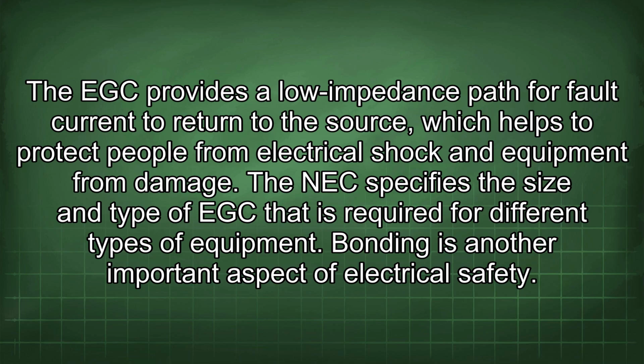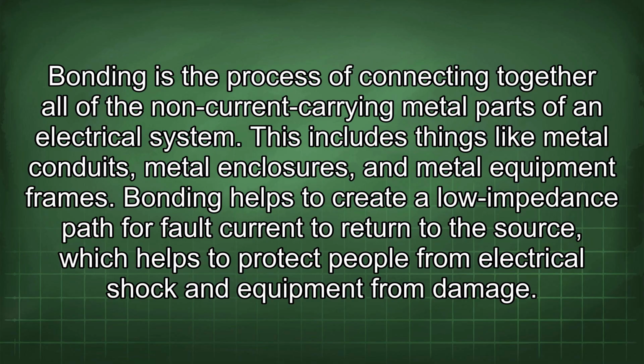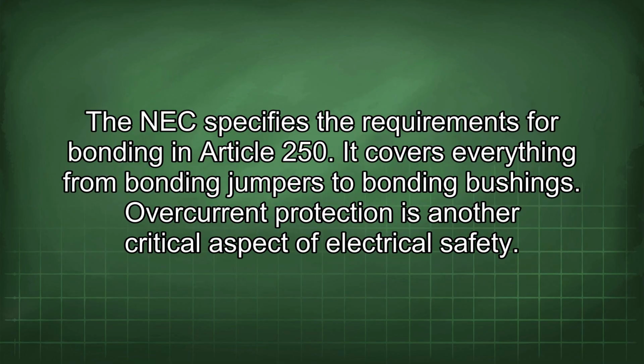Bonding is another important aspect of electrical safety. Bonding is the process of connecting together all of the non-current carrying metal parts of an electrical system. This includes things like metal conduits, metal enclosures, and metal equipment frames. Bonding helps to create a low impedance path for fault current to return to the source, which helps to protect people from electrical shock and equipment from damage. The NEC specifies the requirements for bonding in Article 250. It covers everything from bonding jumpers to bonding bushings.